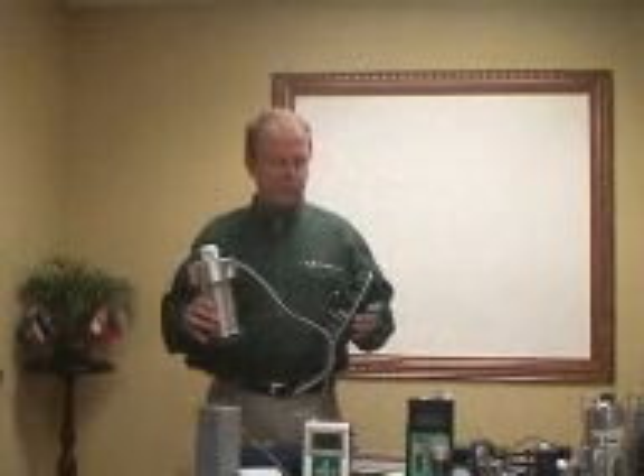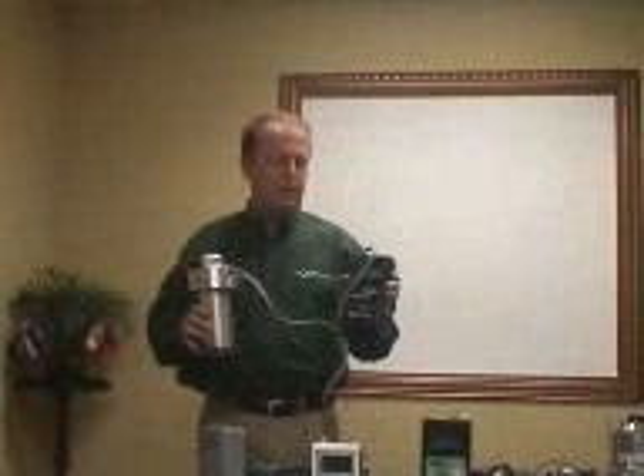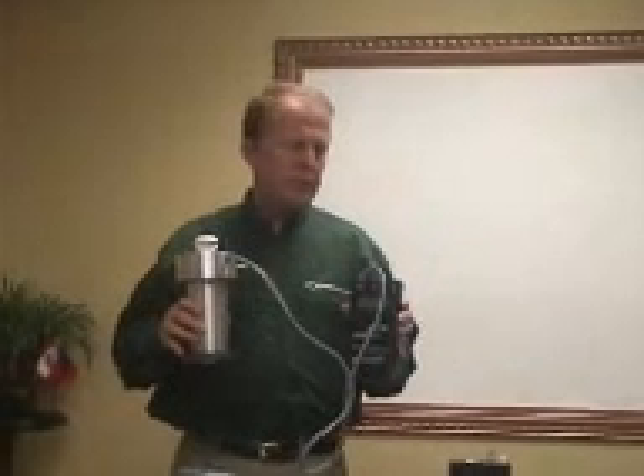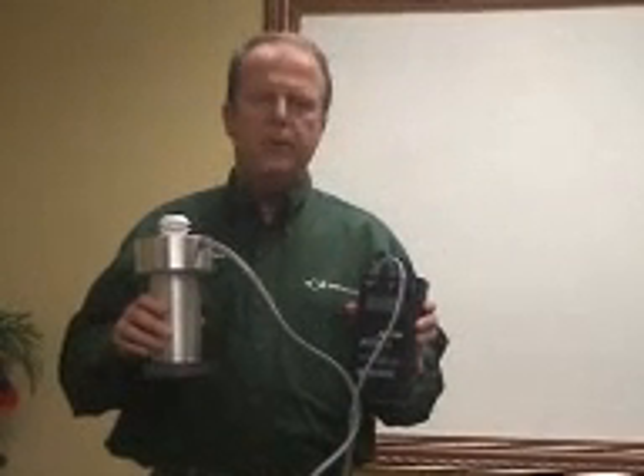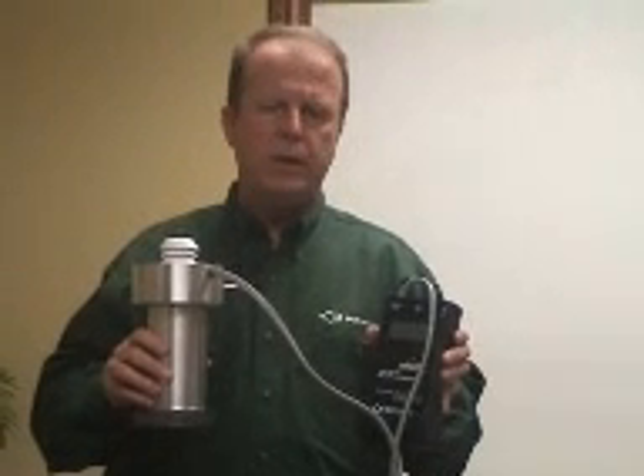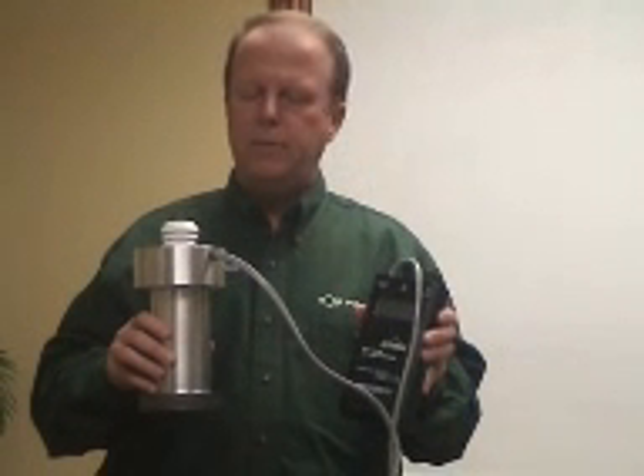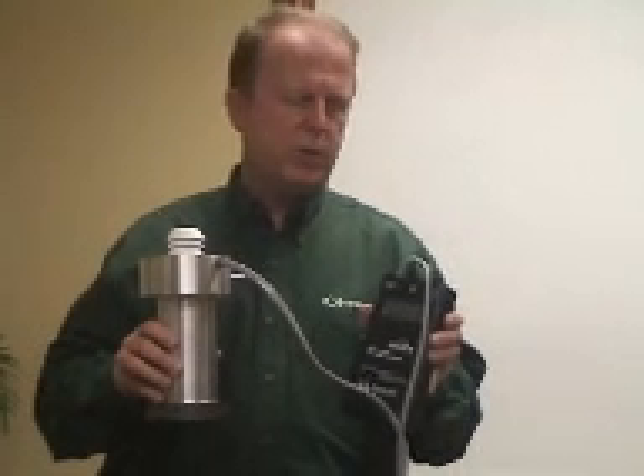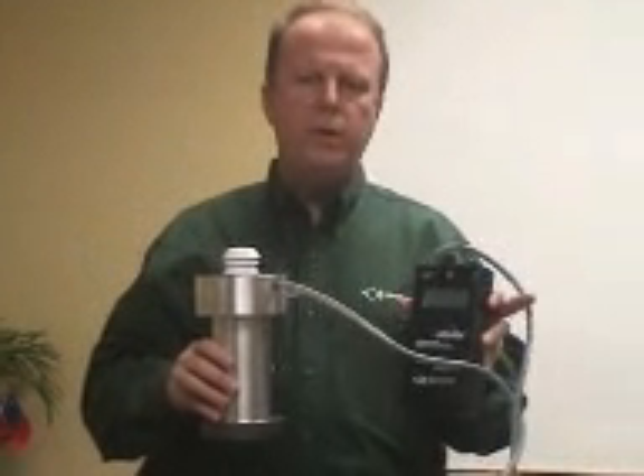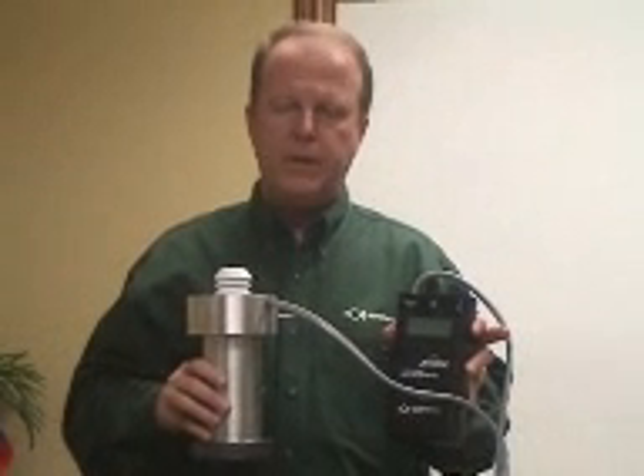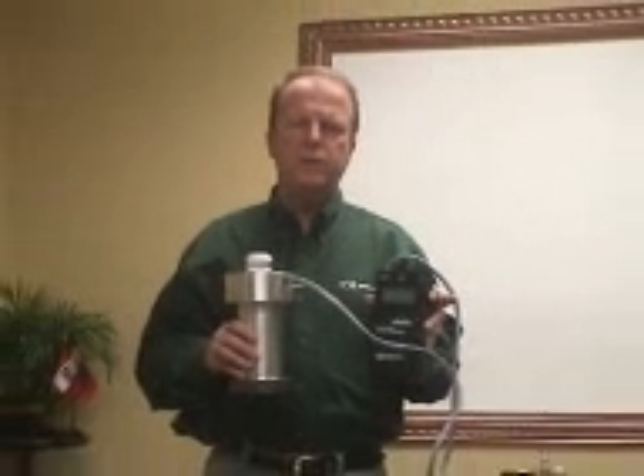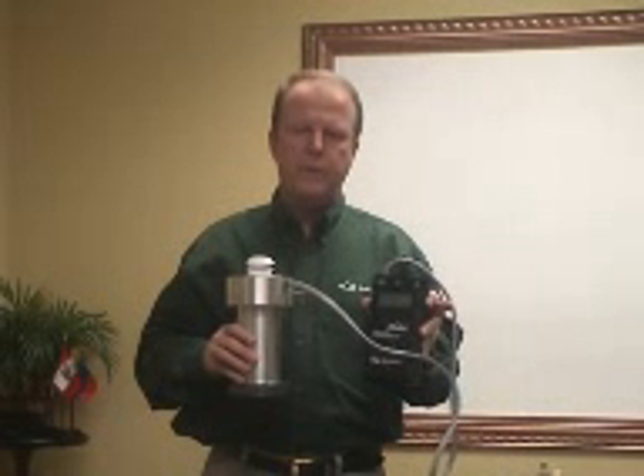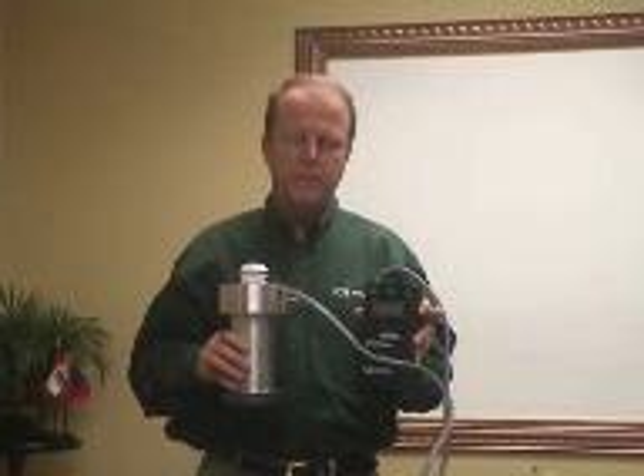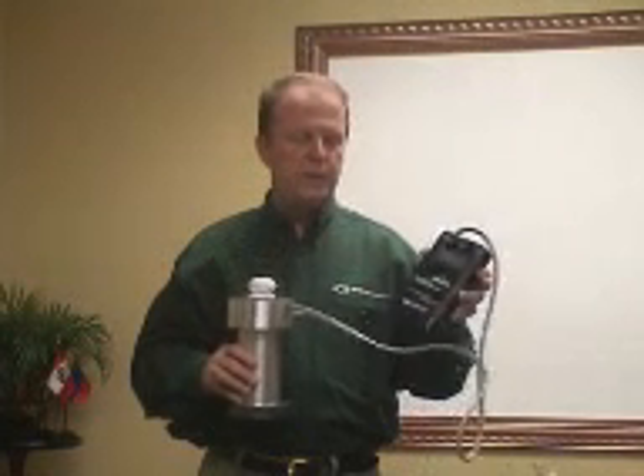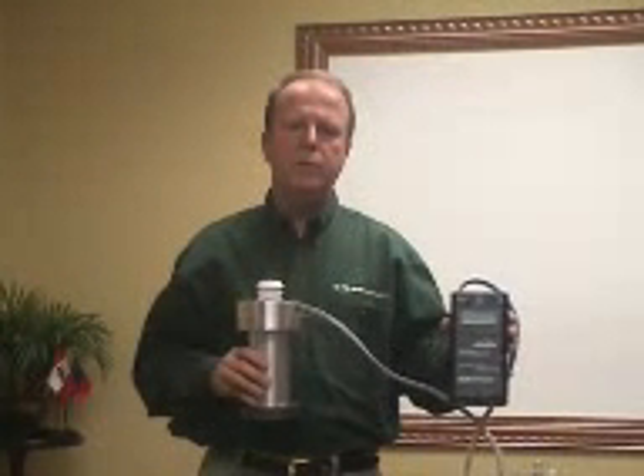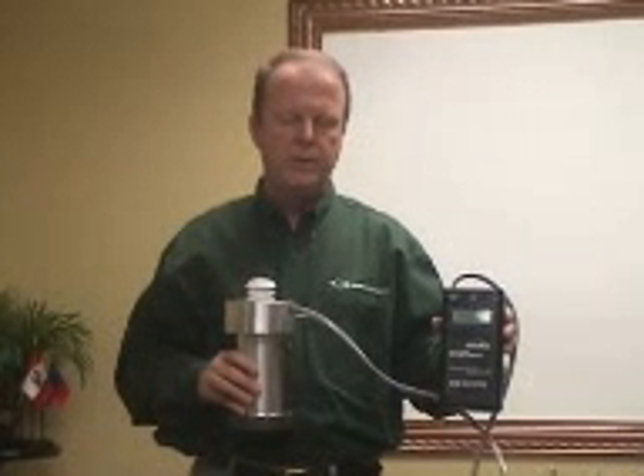what we are really happy to show you today, which is what we call our High-Vol calibrator. The High-Vol Cal is an electronic flow calibrator that was designed by BGI at the direction of the U.S. Environmental Protection Agency as a no-moving-part electronic calibrator that can be used to replace the historical plates and orifices that are very cumbersome and tend to leak. And this is a complete system based on the proven technology of the 3 other calibrator models that BGI makes.